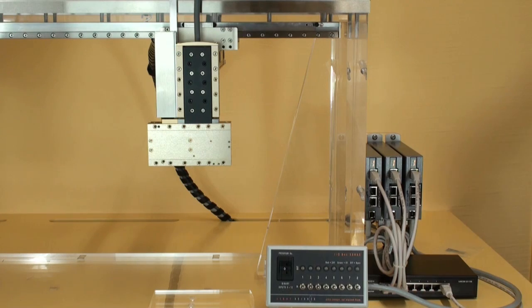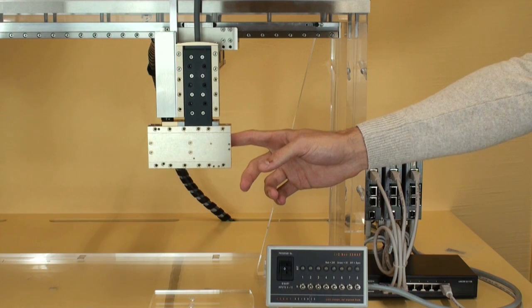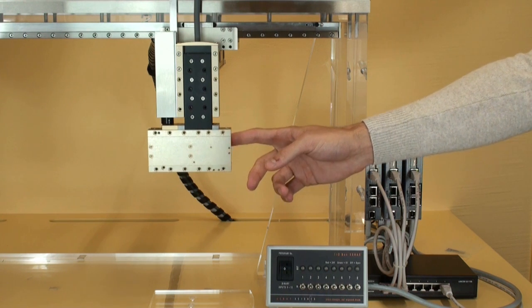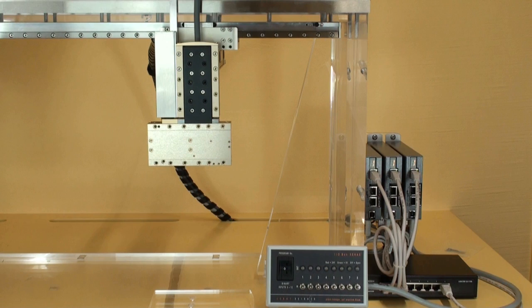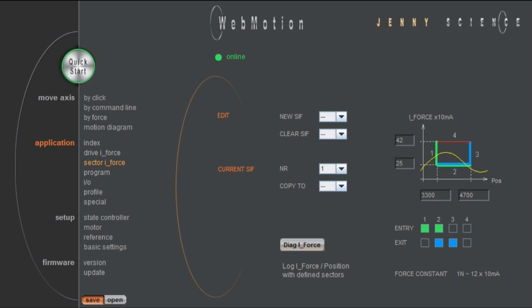Being freed of all those forces, the slider of the motor is perfectly balanced and in a floating state. This calibrated state is fundamental to precisely measure the real forces which are applied to the linear motor by the application process. In order to be able to determine if a process has been completed correctly, we can define up to 10 force sectors with which we would like the force-way curve to comply with.